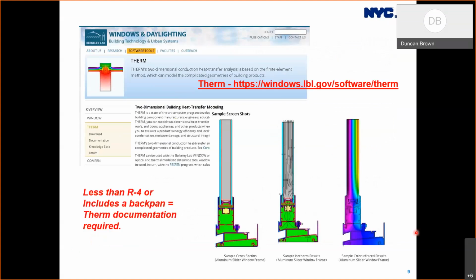So if your wall construction doesn't fall within that table, then documentation using a program like Therm must be used. So if your insulation is less than R4 or your spandrel panel includes a backpan, then Therm documentation would be required.